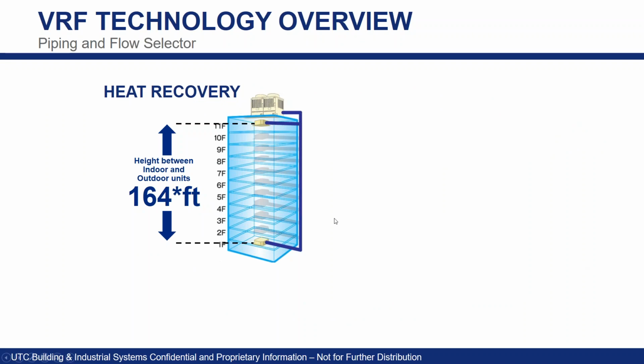Piping. So if you guys bring an application to us, there is going to be some questions, right? We need to determine what you're actually looking at, what the application needs, and building type. Where we're going to put the condensing units. Are we going to put them on the roof? Are we going to put them on grade? Do we have a large floor plan that we're trying to stretch pipe across? There's going to be a lot of questions because there are limitations to VRF. Is it a little bit more flexible than a traditional split system? Sure, but there are some caveats and we need to be careful.